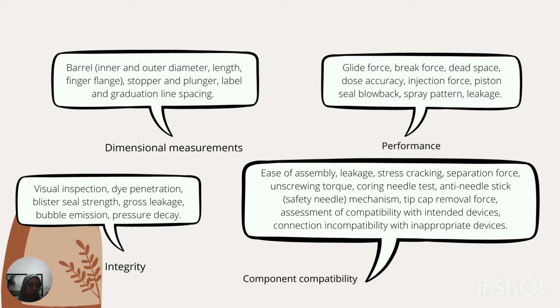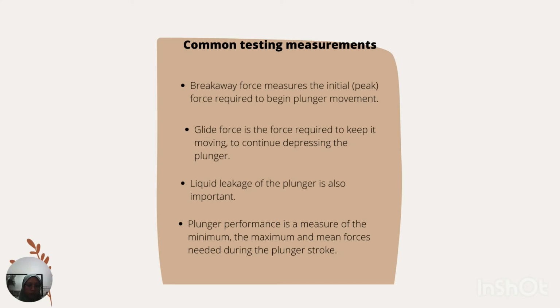And lastly is the integrity. During the test method, it is important to have the visual inspection, dye penetration, blister seal strength, gross leakage, bubble emission, and pressure decay. And next, the common testing measurements.